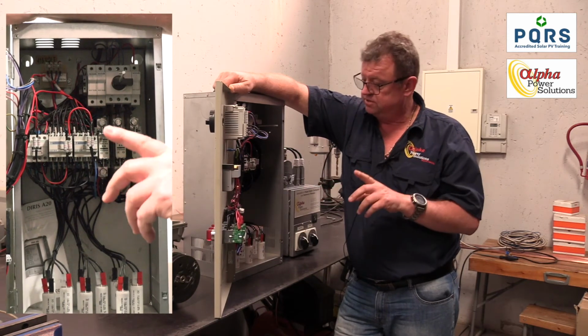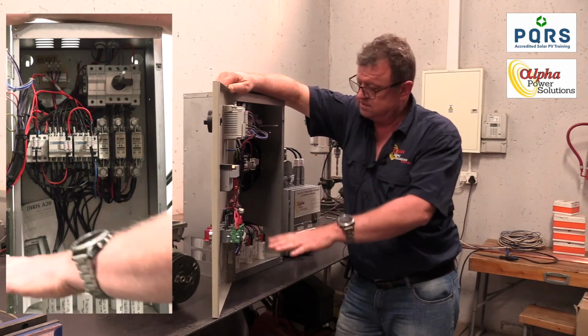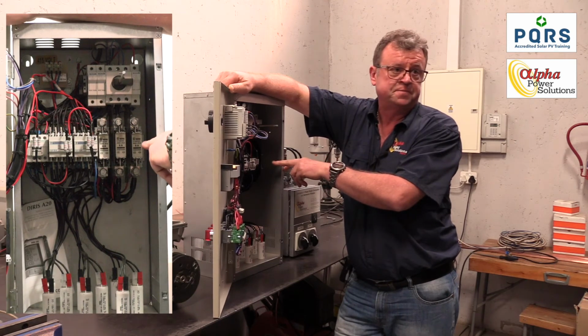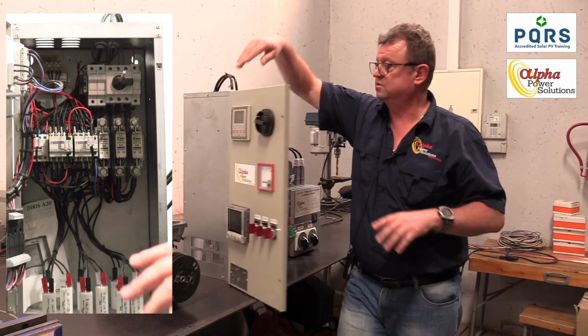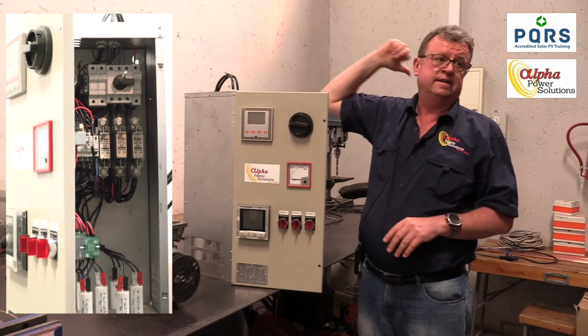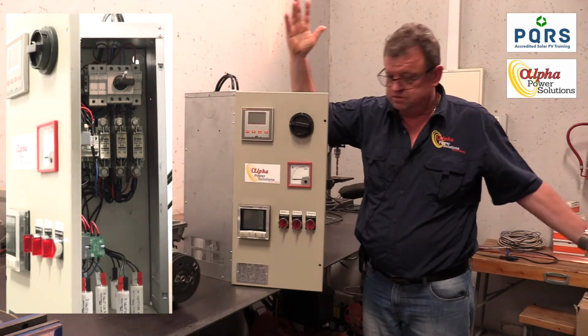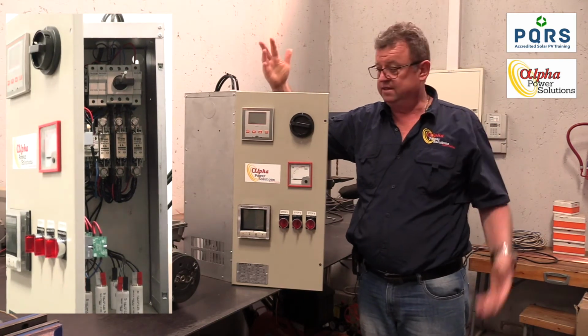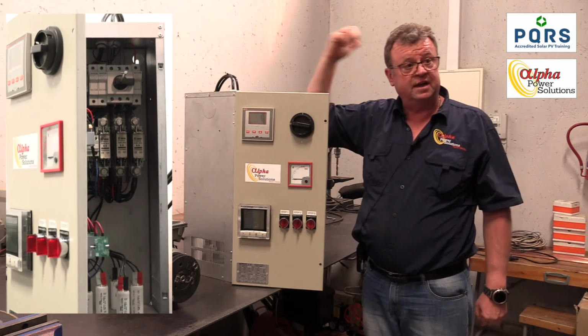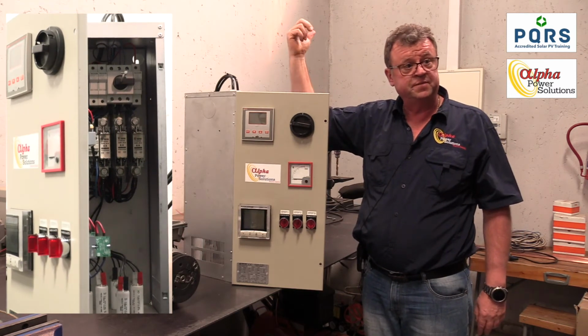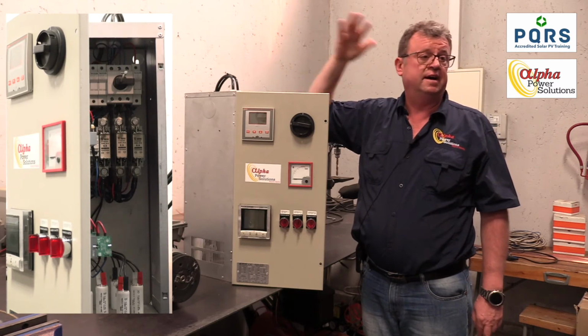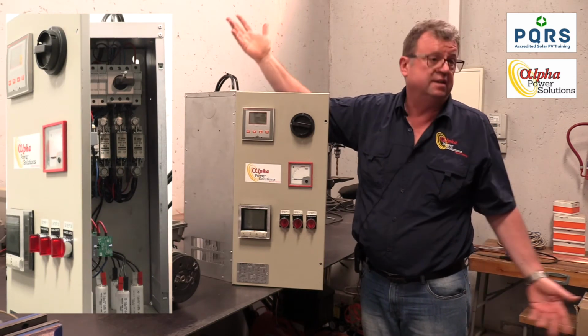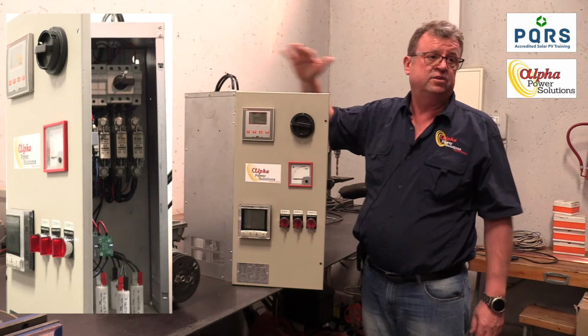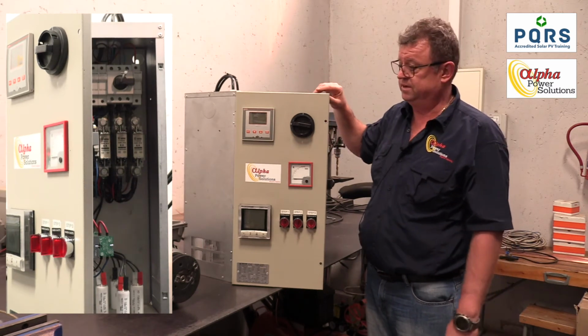So you rely on the main breaker to trip in case of an event here. And the danger is, this system is protected by fuses. But if there is a cable fault between here and the main bus bars, somebody drops something on a cable or whatever, you then rely on the main breaker. So your fault level will be much higher, everything will be much higher, and it is illegal. So you cannot do that. That's the first point that I want to point out.